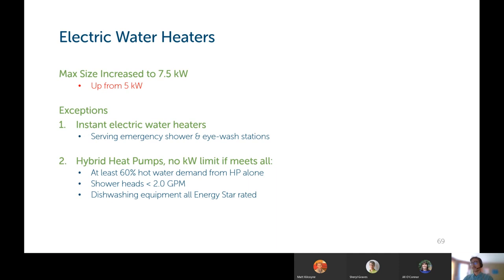Electric water heaters. The maximum size of an electric water heater has increased to 7.5 kilowatts. That's up from 5 kilowatts in the previous code. Exceptions to this are instant electric water heaters serving emergency shower and eyewash stations, which can be larger than that. And hybrid heat pumps have no kW limit if they meet all of these requirements. At least 60% of the hot water demand can be met from just the heat pump portion of the water heater, not the electric resistance element.